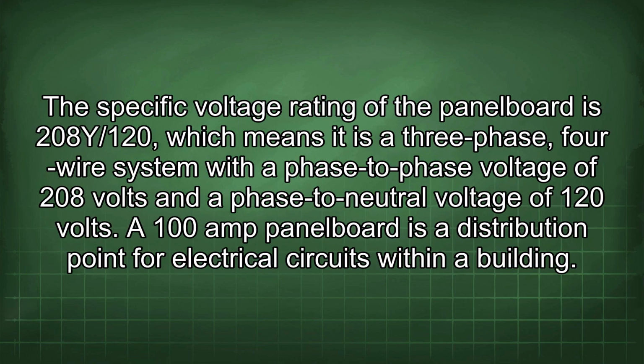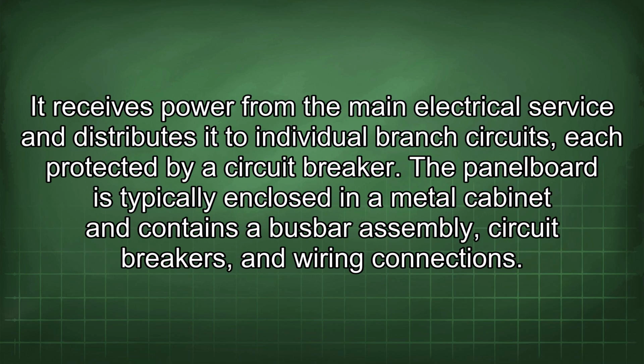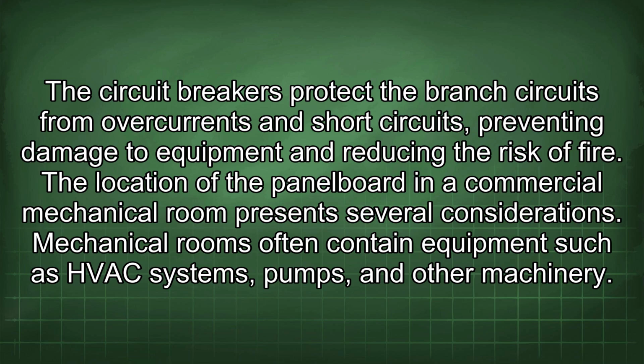The specific voltage rating of the panelboard is 208Y/120, which means it is a 3-phase 4-wire system with a phase-to-phase voltage of 208 volts and a phase-to-neutral voltage of 120 volts. A 100 amp panel board is a distribution point for electrical circuits within a building. It receives power from the main electrical service and distributes it to individual branch circuits, each protected by a circuit breaker. The panel board is typically enclosed in a metal cabinet and contains a busbar assembly, circuit breakers, and wiring connections.